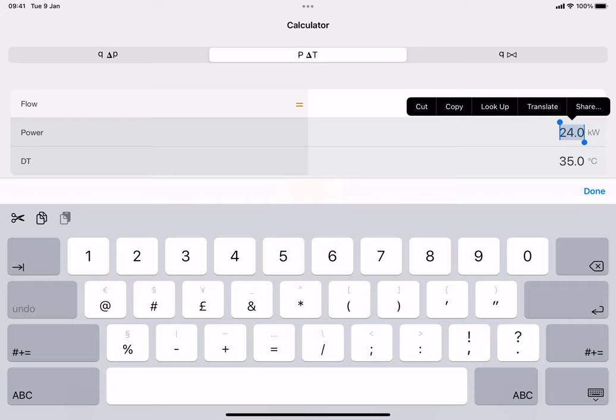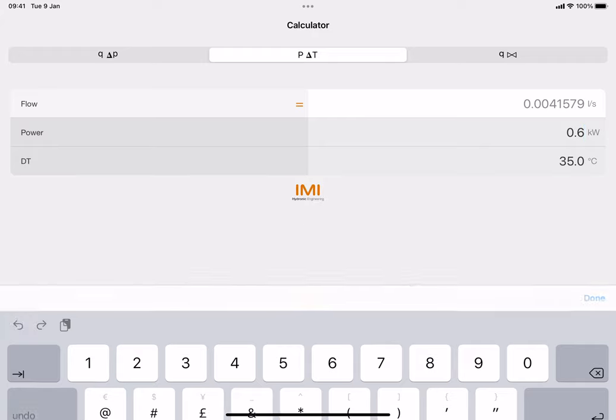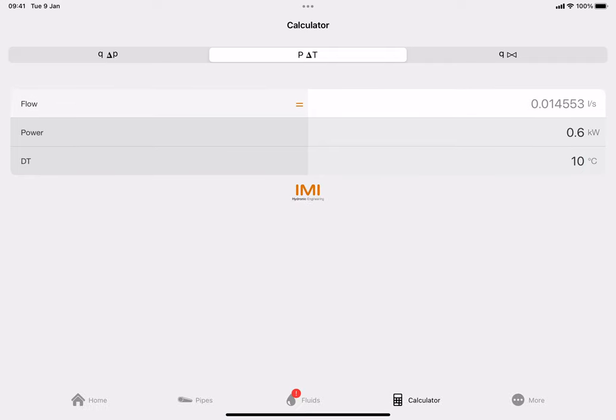Let's say we had a heat loss in a bedroom of 600 watts - we put that in as kilowatts so we type in 0.6. We look at our Delta T: if we're looking at 55 degree flow temperature and 45 degree return temperature we've got a Delta T of 10 degrees, so we put in 10 degrees and click done. That now tells us that to carry 600 watts through to that radiator at a Delta T of 10, we need 0.014553 liters per second running through that pipe.